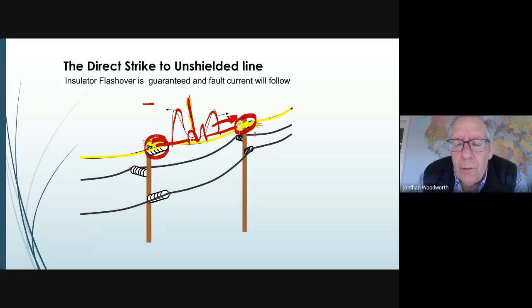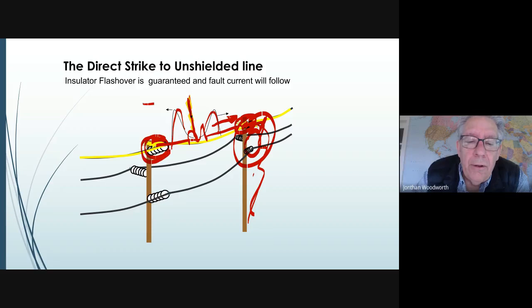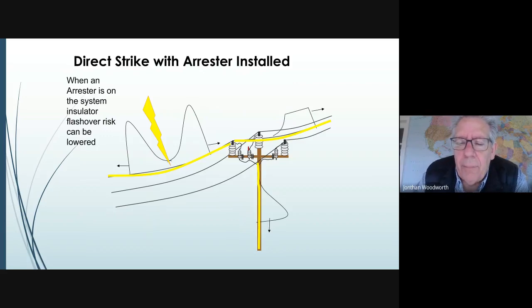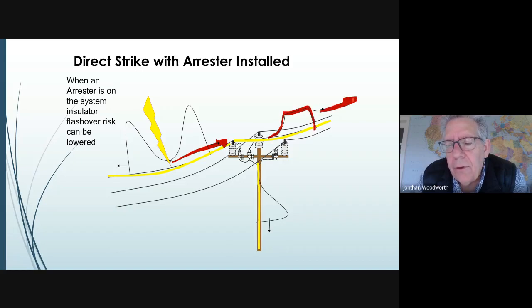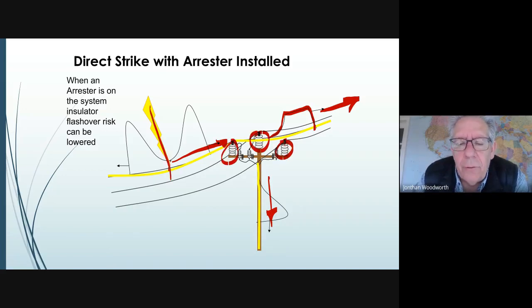If there was a transformer on this distribution line, of course, we would have an arrestor, and you probably wouldn't have this flashover. It would just be diverted to ground. This one over here might still flash over, but not where the arrestor is. For example, here are 3 arrestors. These arrestors are here for line protection. In this case, the owner of this line didn't want any flashover on his system, so he installed arrestors even without equipment there. The surge comes down the line, it gets to the arrestors, and the arrestors clamp it. The clamped surge continues on. Some of the current surge goes to ground, but there's no flashover, even though there was a direct strike to the line.